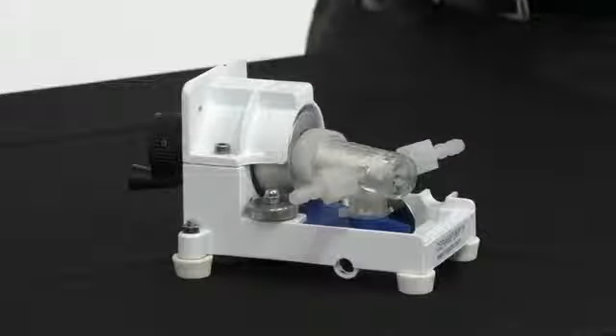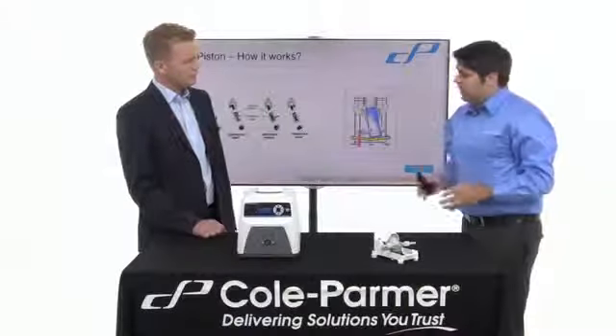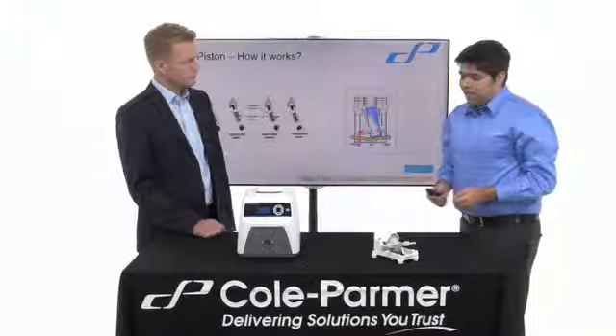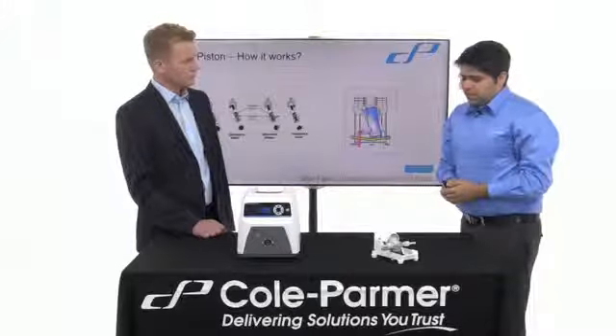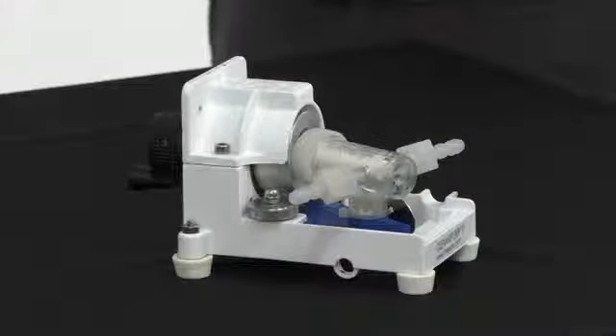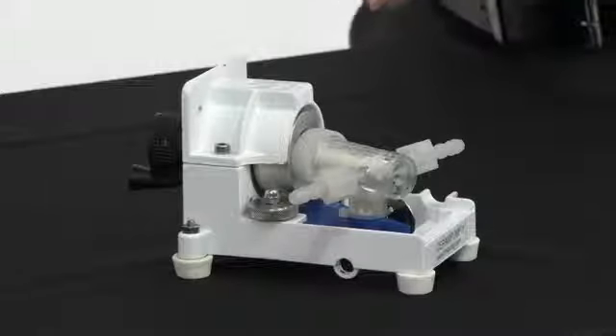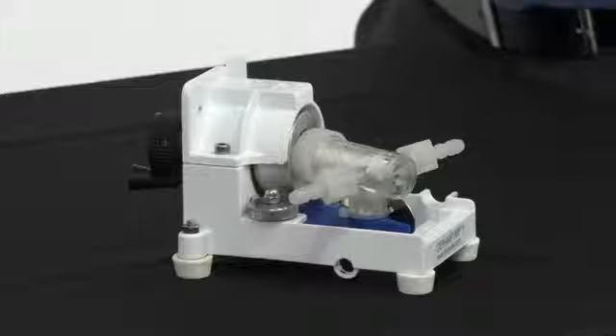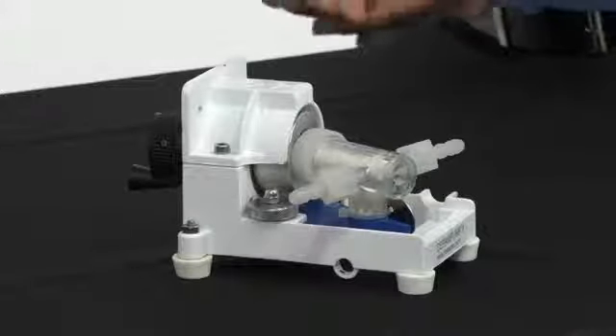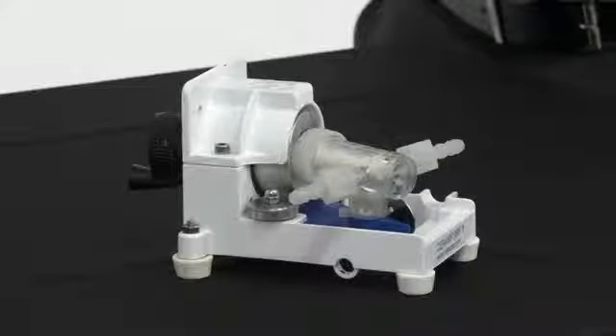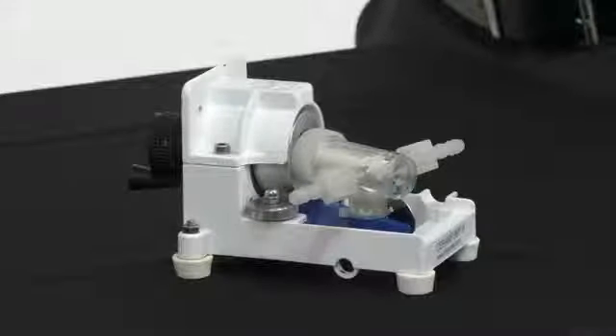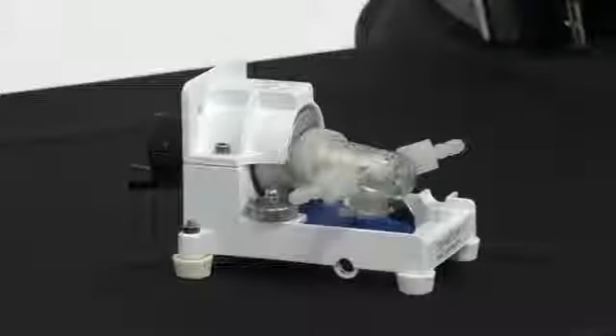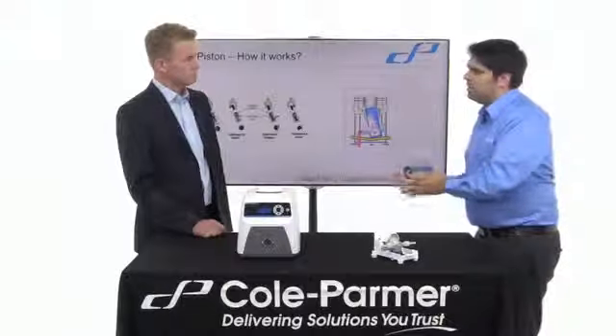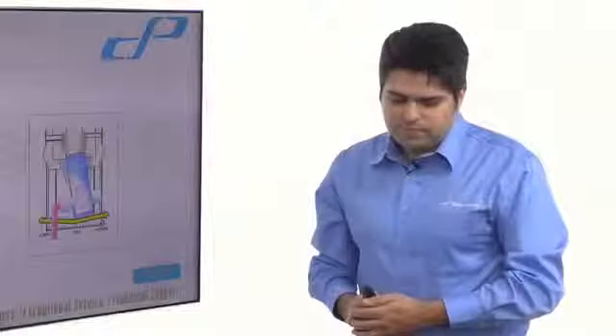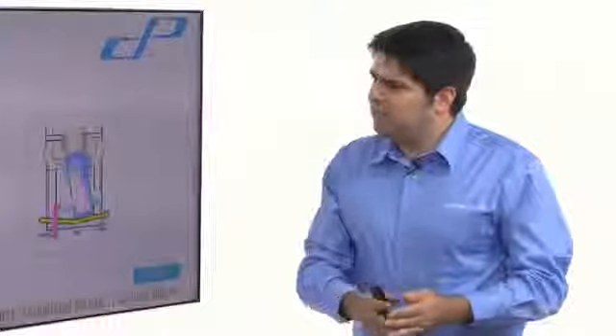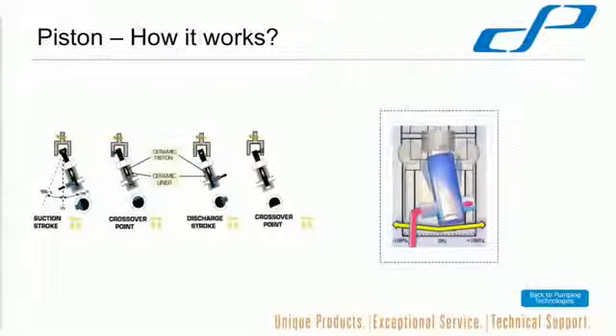Right, and how does this compare to the gear pump technology? In terms of flow rates, they are very similar, actually, and in terms of pressure, they're similar. But this one will give you pulsation. The gear pump doesn't give you pulsation. But having said that, this pump has the better repeatability, so it would just carry on, low maintenance. And if you have a varying back pressure, say something happens downstream and causes a slight blockage, this pump will carry on pumping at the same speed. The gear pump might drop a little bit. I think that's one of the main benefits over the gear pump, although you do get the pulsation.